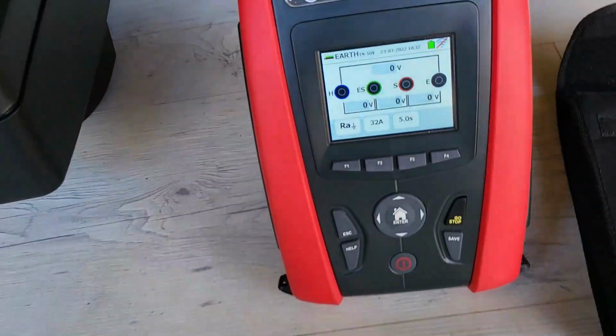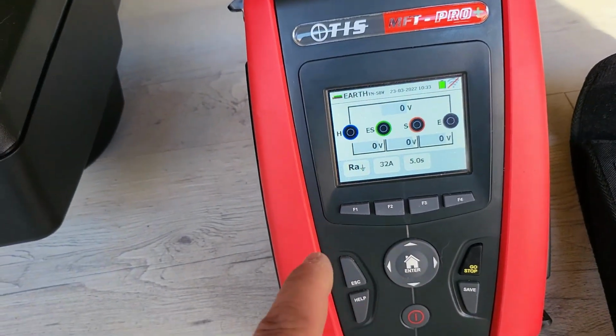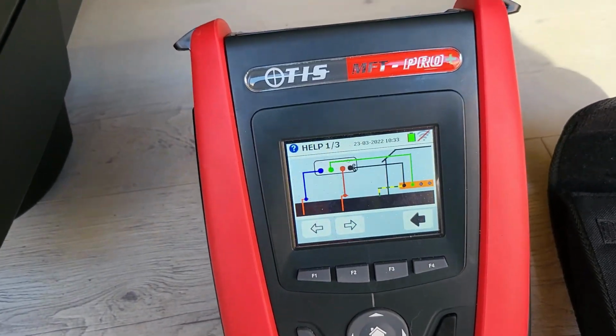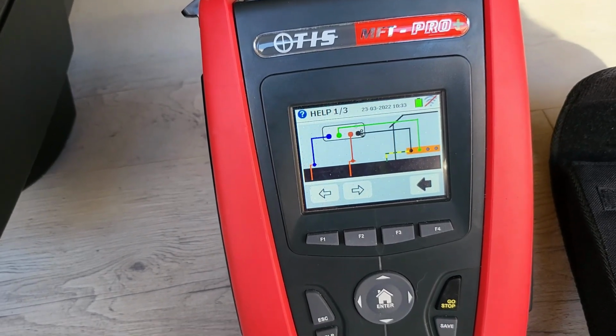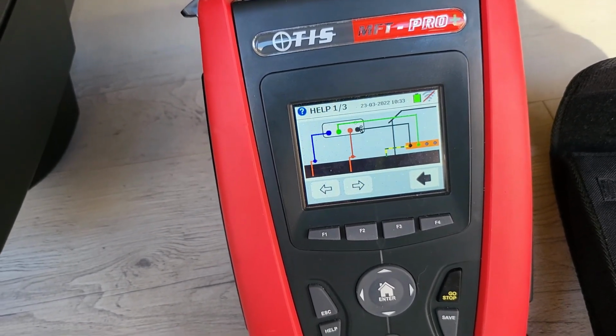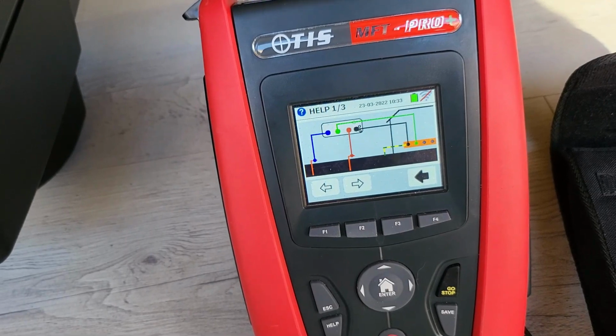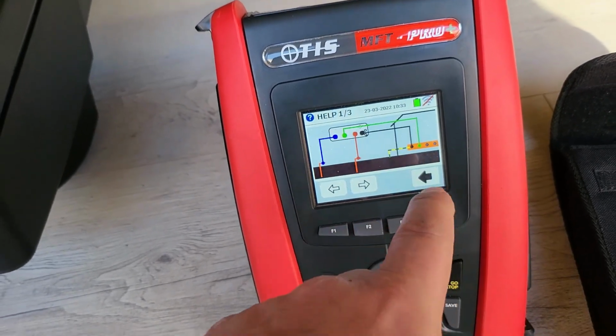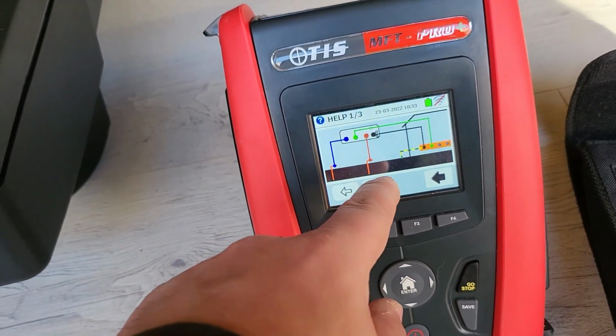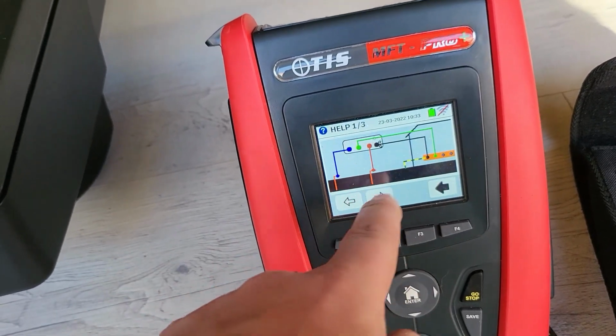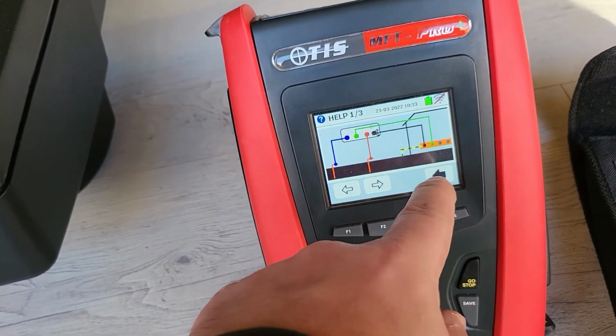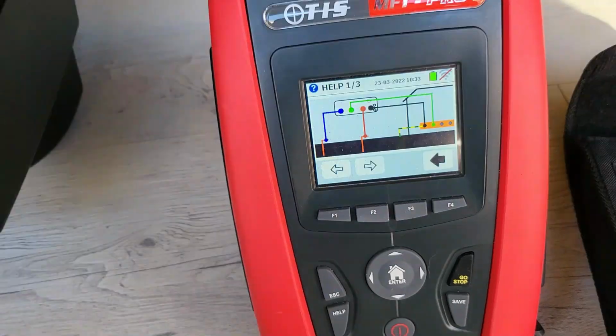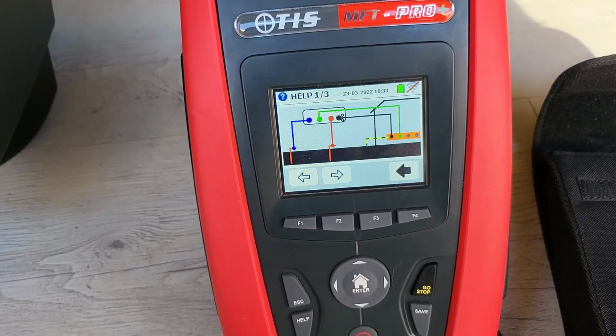Note with the TIS tester, if you're not familiar with this one, it does give you a help menu. So you can see we've got the 3-wire earth testing for when you're doing your RA measurement. This will be the one that most people are familiar with. So you obviously go onto your earth rod and then take your spikes out, and this is the distances that we're on about. So we've got a 1.2 metre rod, we need 12 metres, and maybe go a bit further and have a play around with this.